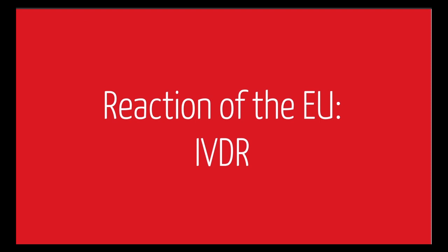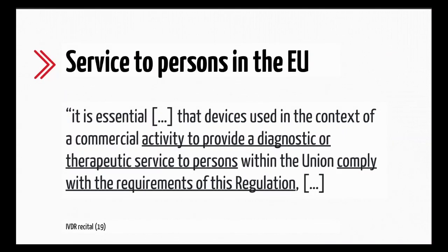What was the reaction of the EU? It was the in vitro diagnostic medical device regulation. And there it is stated that for service to persons in the EU, it is essential that devices used in the context of a commercial activity to provide diagnostic or therapeutic service to persons within the Union comply with the requirements of this regulation. So that means if you have a laboratory service, the service needs to comply with the requirements of the IVDR.